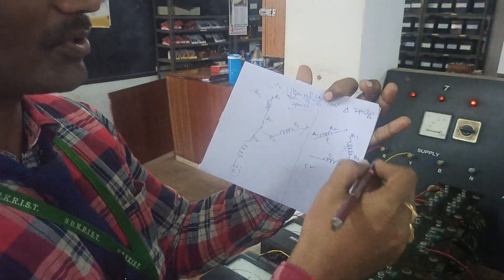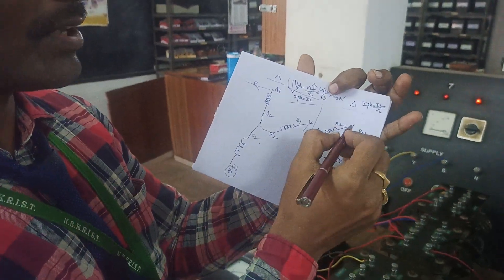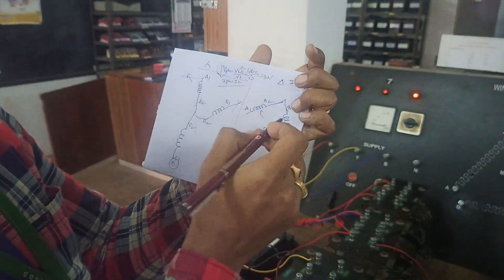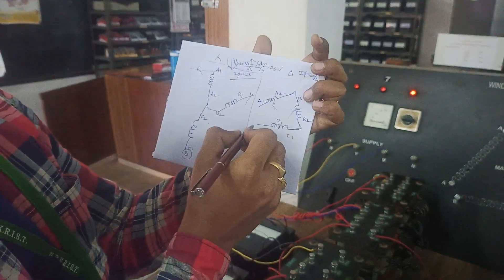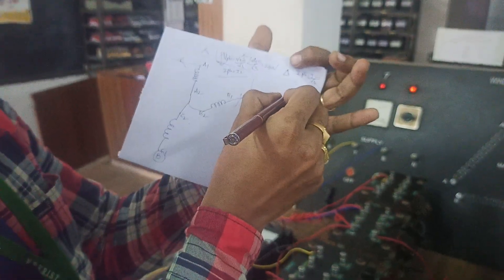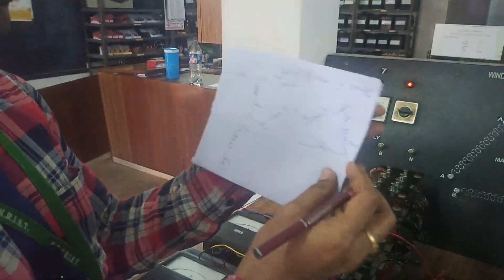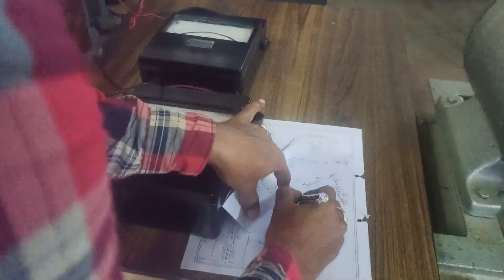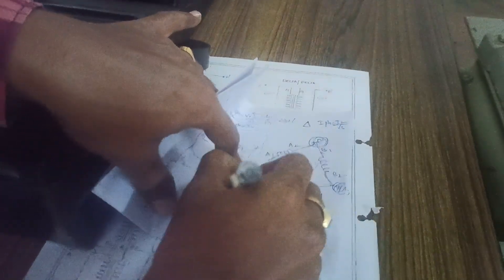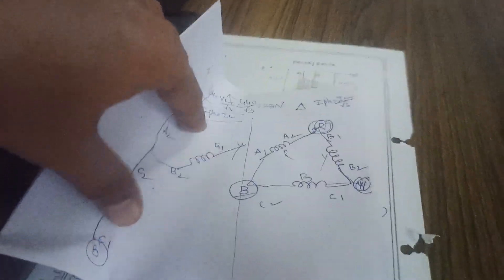How to connect this in delta fashion: connect A2 terminal to B1, connect B2 terminal to C1, connect C2 terminal to A1, and you start exiting here as R, Y, B. R, Y, B are three phases phase shifted with 120 degrees.